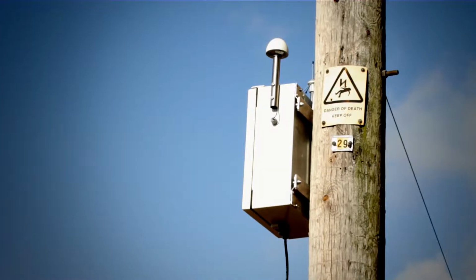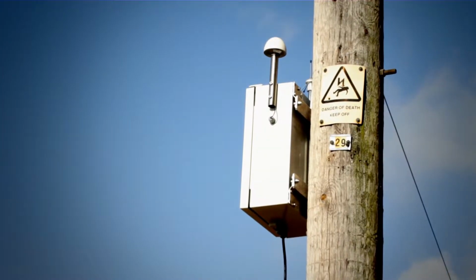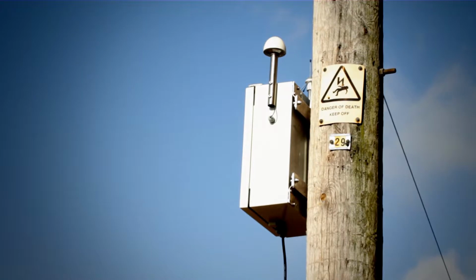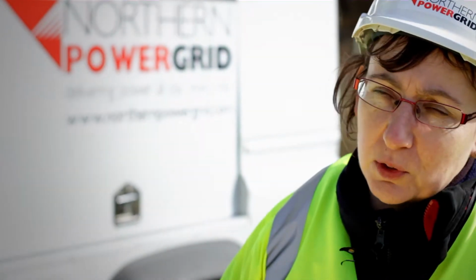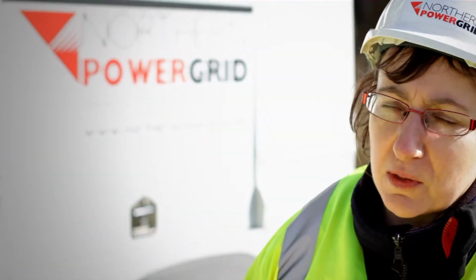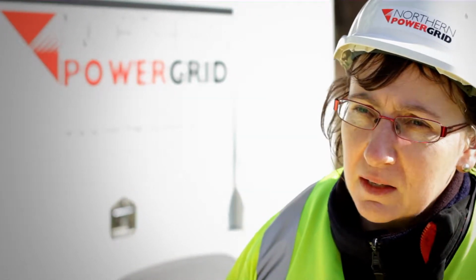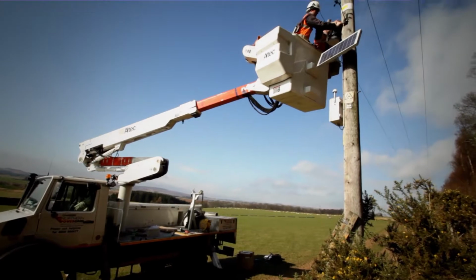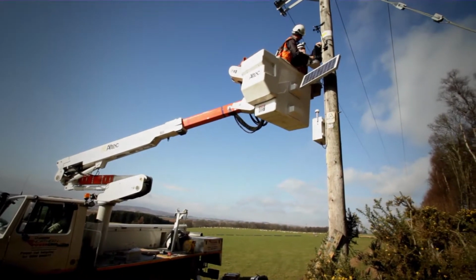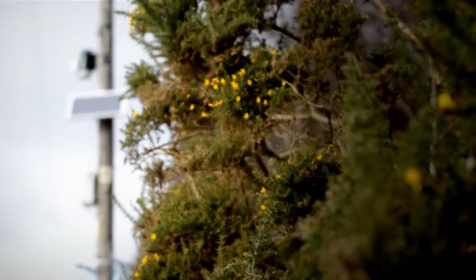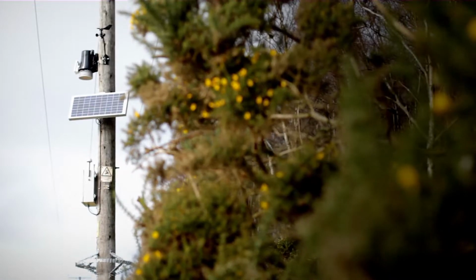So what we've got here is a weather station that looks at the amount of sun falling on the line, it looks at the wind speed, which has a chilling effect, and it records that temperature, and it records the actual temperature of the line and the current going through the line as well. We get all that data back, and then we can understand how weather affects the real capacity of the line. We've given several companies the opportunity to air their wares basically.